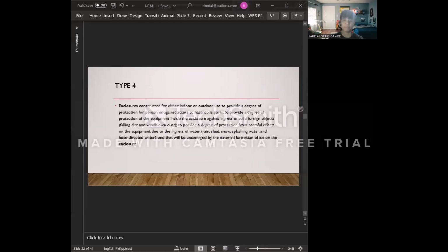Next type is type 4 enclosures. So, type 4 enclosures are constructed for either indoor or outdoor use to provide a degree of protection for personnel against access to hazardous parts. Next is to provide a degree of protection of the equipment inside the enclosure against ingress of solid foreign objects, for example, yung falling dirt and wind-blown dust. Next is to provide a degree of protection from harmful effects of the equipment due to the ingress of water, for example, rain, sleet, snow, splashing water, and hose-directed water. So, may hose-directed water na siya. And that will be undamaged by the external formation of the ice on the enclosure.